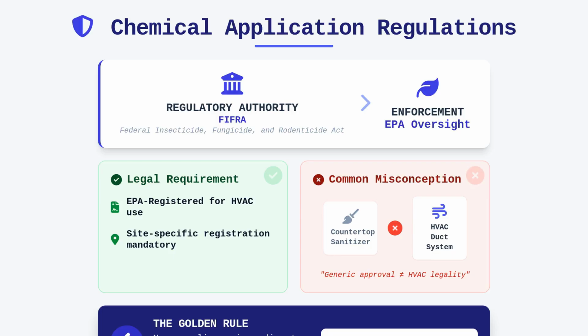It is a fundamental requirement that any product we introduce into a HVAC system must be EPA registered specifically for that use. A common misunderstanding in the field is that a product approved for sanitizing a kitchen countertop is inherently safe or legal to use inside a metal or fiberglass duct. In reality, the EPA requires site-specific registration, meaning a product must explicitly list HVAC systems on its label to be used legally. Always remember that the label is the law. Applying a product in a manner inconsistent with its label instructions is a direct violation of federal legislation.